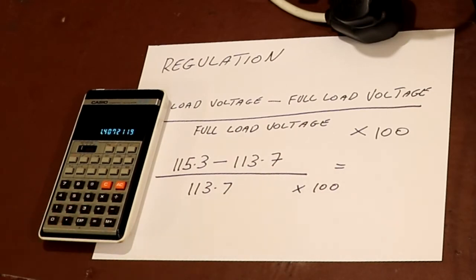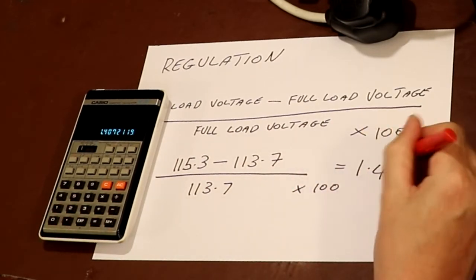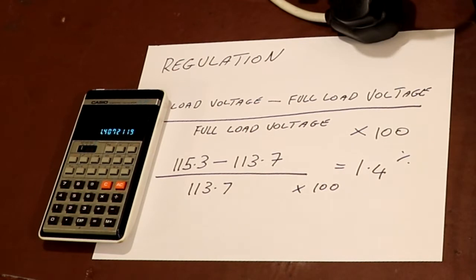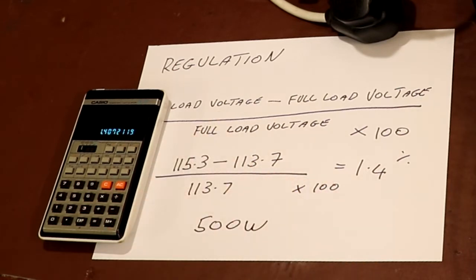That equals a regulation of 1.4%. Now for a transformer that's very good, but unfortunately we have a slight fly in the ointment, which is that voltage regulation should be done at the full rated load of the transformer, which for this particular transformer I think is probably 1000 watts. Unfortunately my radiator only presented a load of 500 watts, so we didn't actually do the regulation test at its full rated load, which is unfortunate.